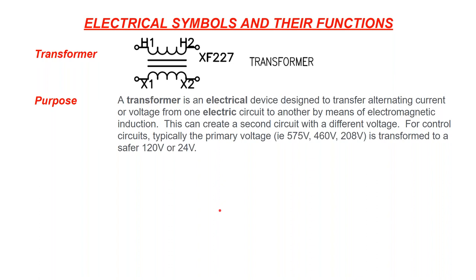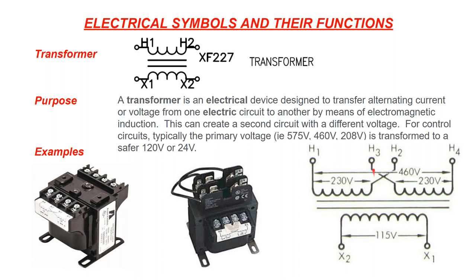A transformer is used to transform the voltage. Often we have three-phase input power going into a panel, and we need to transform that into a safer voltage for control. For example, a transformer diagram may show it can take 460V or 230V and transform it into 115V — that diagram comes right off the transformer itself.